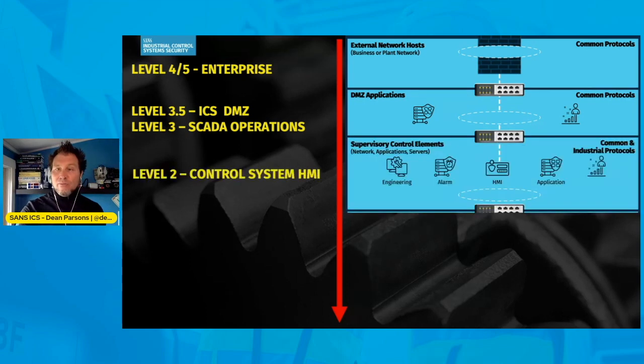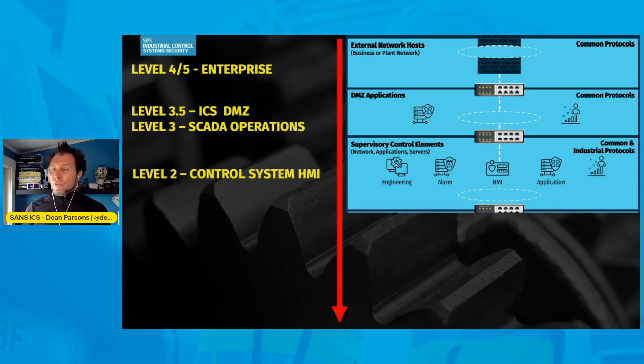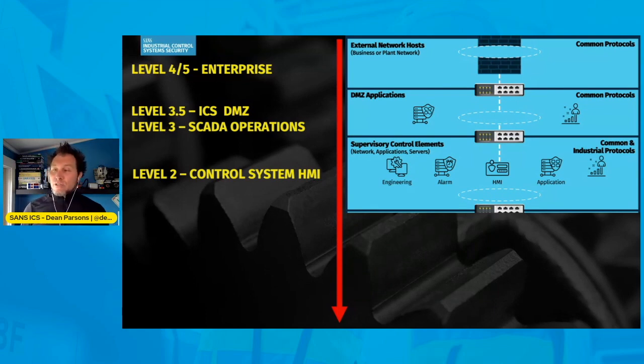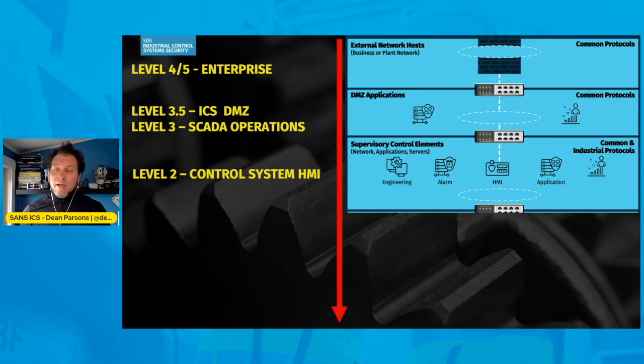Going further down the Purdue to level two, this is your control system area where you have control devices like human-machine interfaces possibly running on Windows OT devices. They interact with controllers and PLCs at level one. Also at level two are alarm servers, engineering workstations, and operator workstations — used to view the process, and possibly to change or program the controllers at level one. An operator sends commands from the HMI at level two, over a control network using industrial protocols, possibly through an OPC service, communicating down to PLCs at level one.